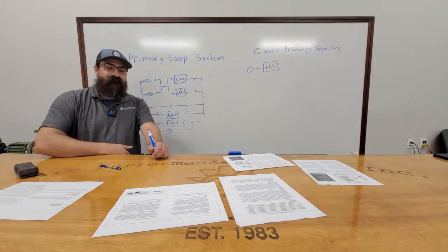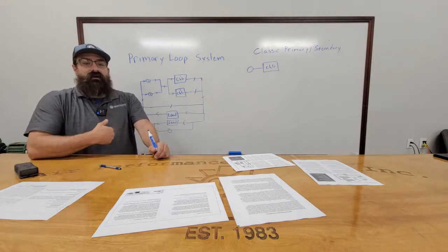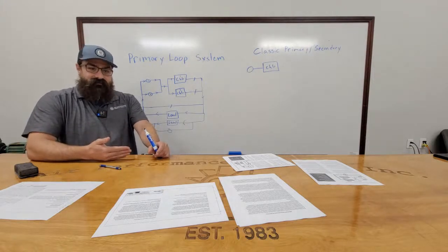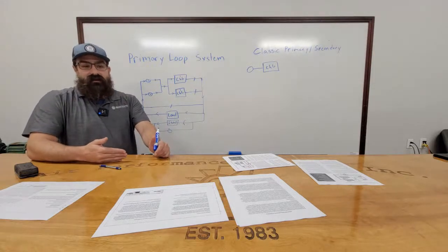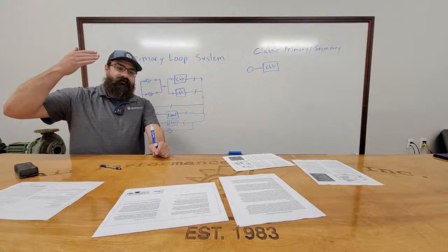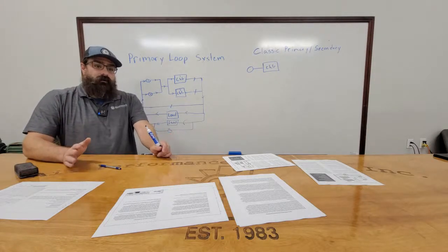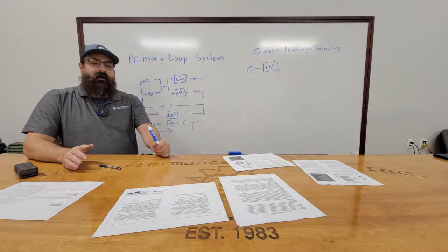But the pumps are down on the first floor of this six-story building. Yeah. We control the pumps. We control the differential pressure with the pumps. I have to have both pumps running in this building to maintain the differential pressure that's required for the air handlers. The building will not maintain on one pump. It just won't. Right, but the chiller doesn't require both pumps.